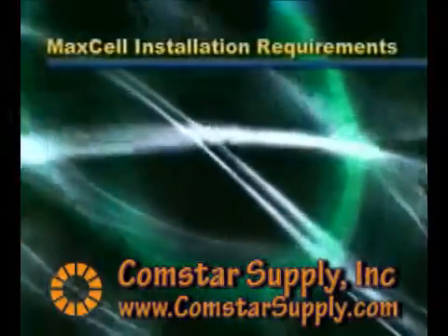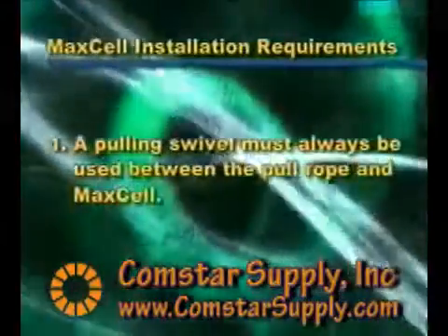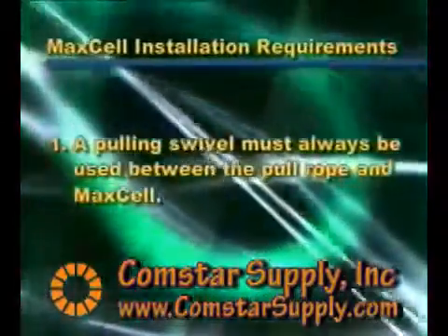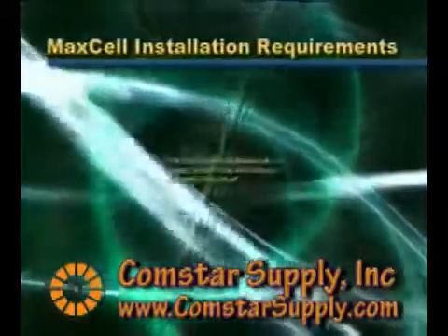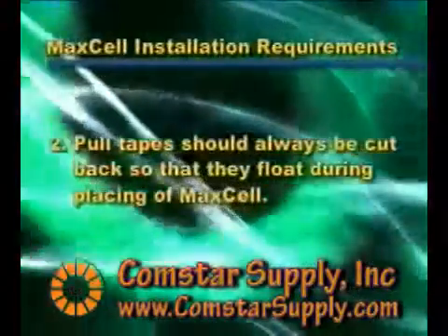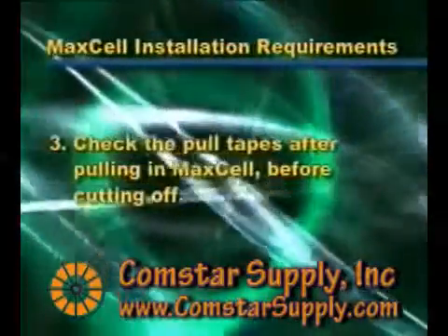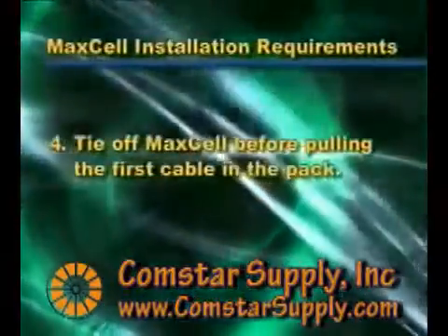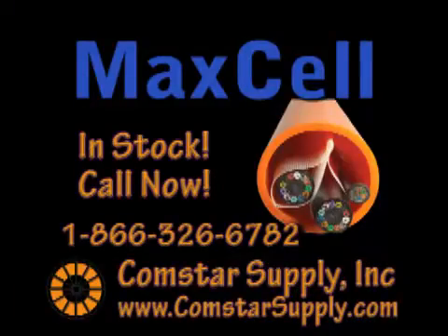MaxCell installation requirements. A pulling swivel must always be used between the pull rope and MaxCell. Failure to do so may result in the pull rope causing the MaxCell to twist excessively and may make it difficult to pull cable. Pull tapes should always be cut back so that they float during the placing of MaxCell. Check the pull tapes after pulling in MaxCell before cutting off — they will float back during the pull. Tie off MaxCell before pulling the first cable in the pack. It is always better to lubricate cable during the pull.